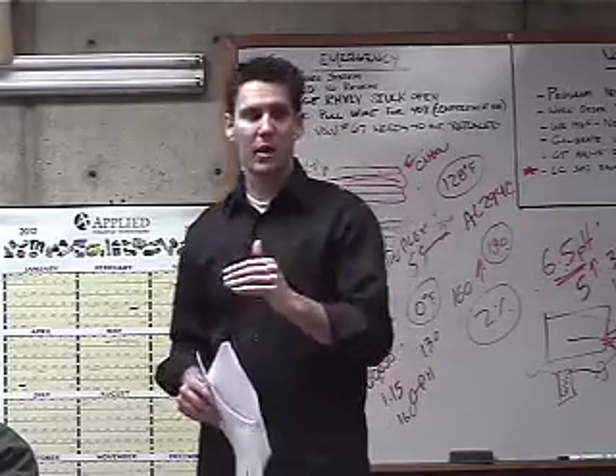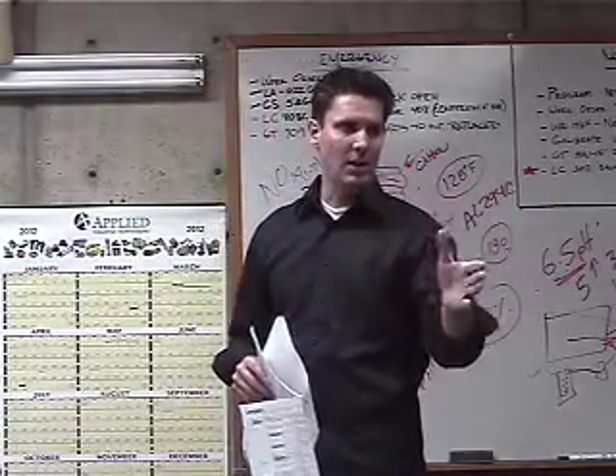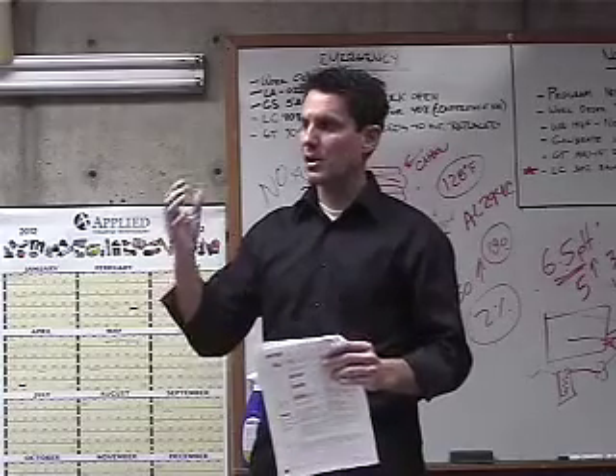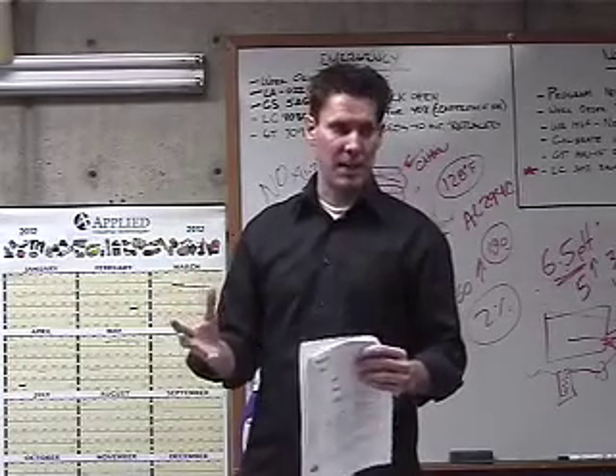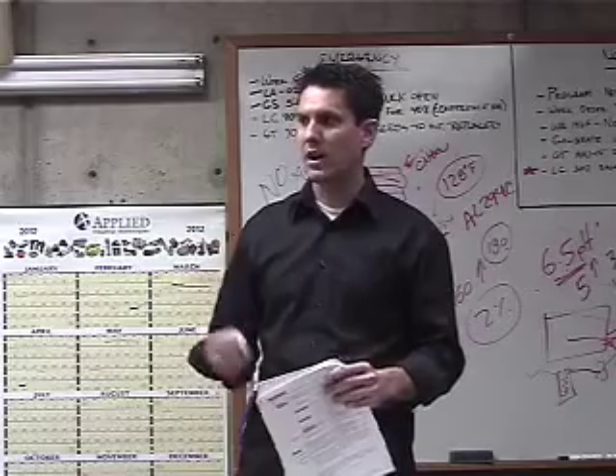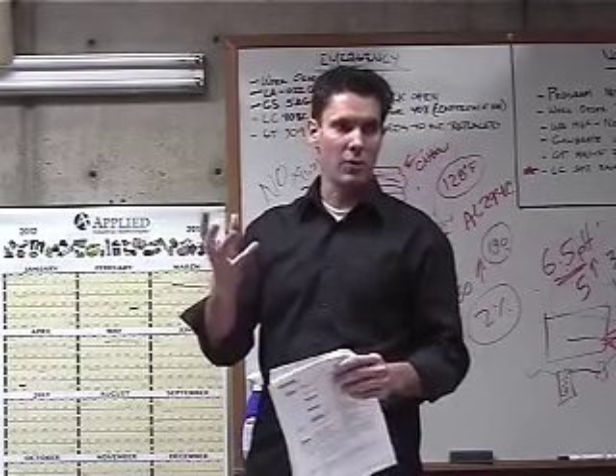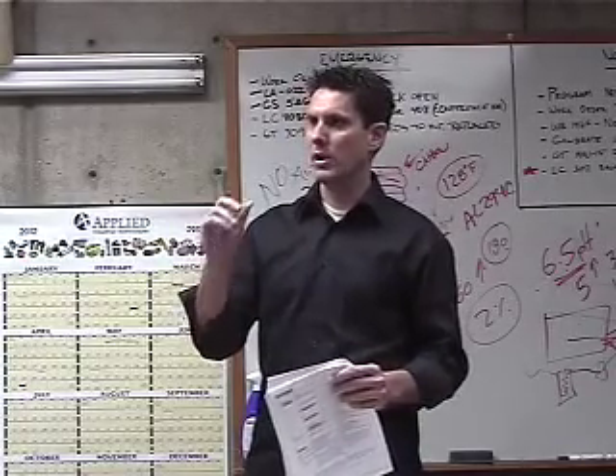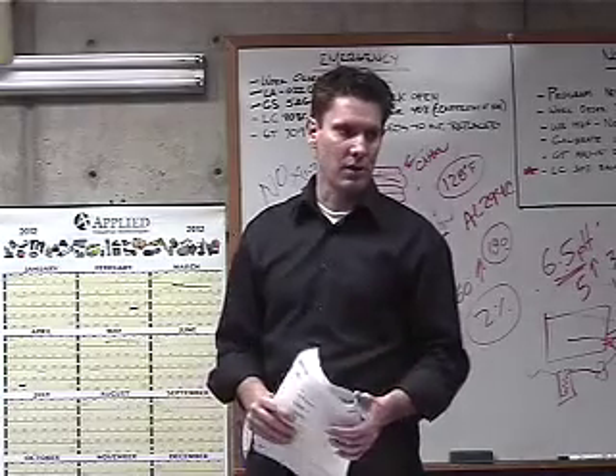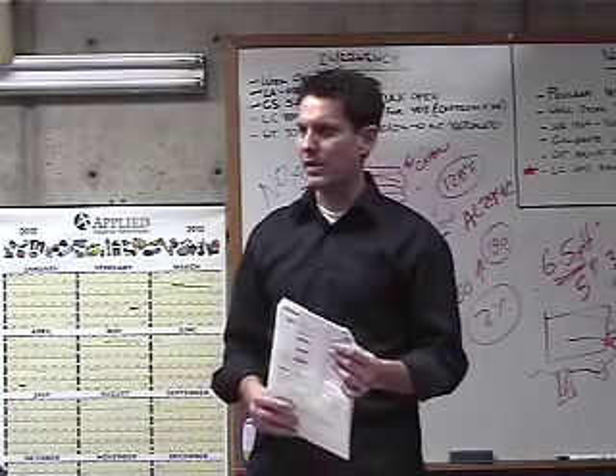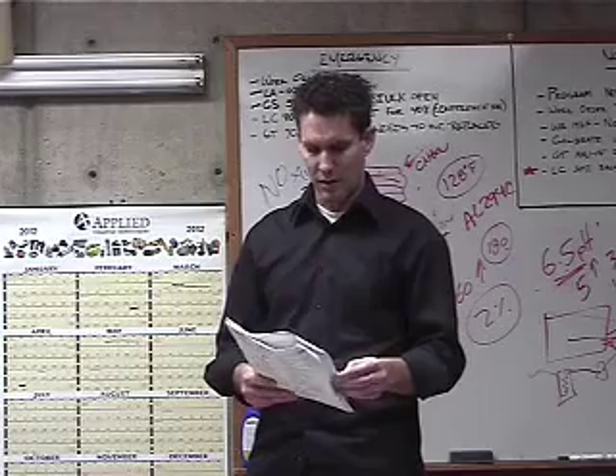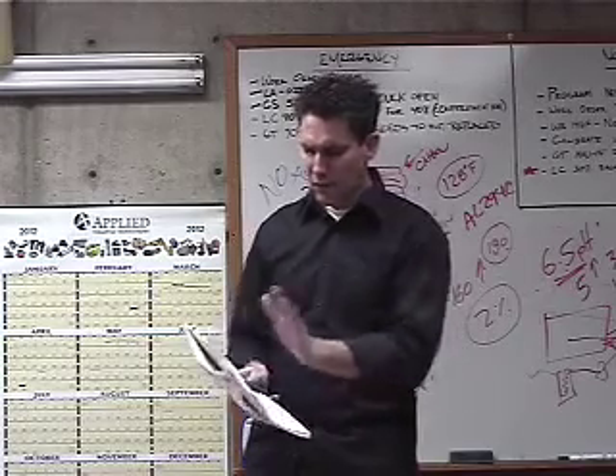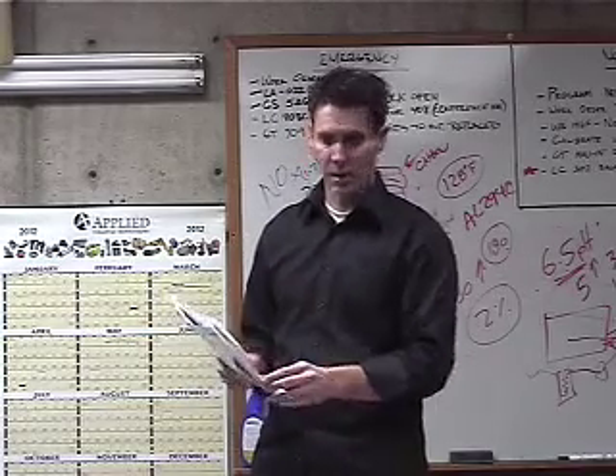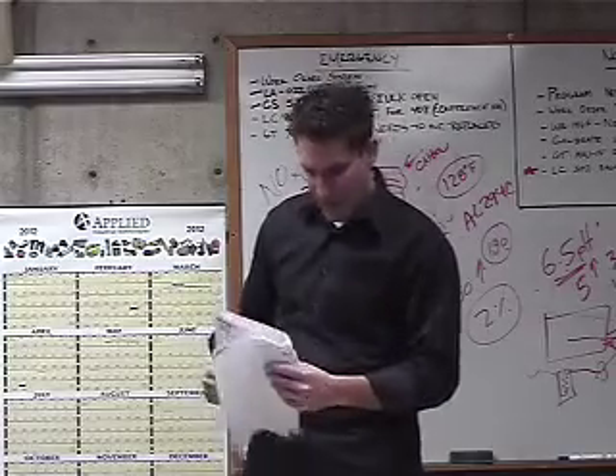The nice thing about this boiler is it's not like some of these other condensing boilers that use residential type stuff. You don't have a hot surface igniter. You've got a nice industrial spark igniter. You've got a Siemens LMV37 controller. It's some pretty heavy grade stuff. So again, that troubleshooting section is pretty good to refer to.